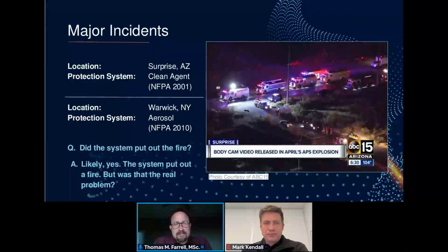That was a large ESS installation protected by a clean agent system designed in accordance with NFPA 2001. With clean agent inside these containers, you have your typical ESS fire, and clean agent was pumped in, which probably put out the fire inside the enclosure, but it doesn't address the enormous amounts of heat generated. Unfortunately, a lot of the clean agents in use in the marketplace today, in the presence of high pressure or high temperature, decompose into flammable, toxic, or acidic gases.